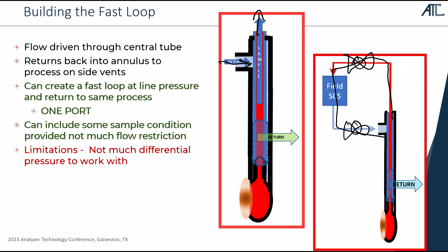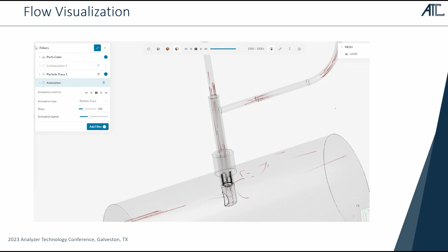The limitations that we have to consider with this is physics is going to determine how much differential we can actually create. Hopefully this animation is going to go. Let's see. There you go. So there's actually a computational fluid dynamics simulation of this probe in operation. Fluid flowing along the pipeline. So you can see the vortices that kind of show up on the back side, but it drives flow up the center side, returns stuff back on the return side, and back into the process pipe.